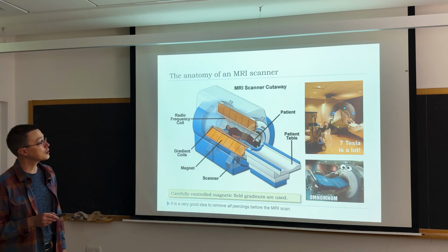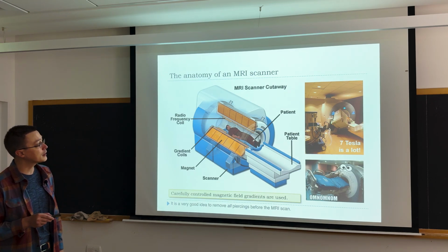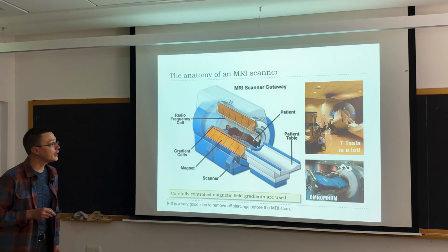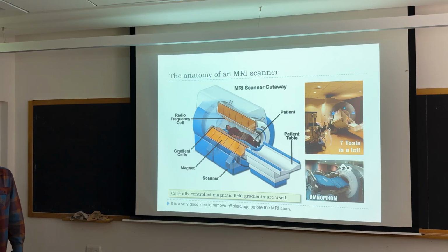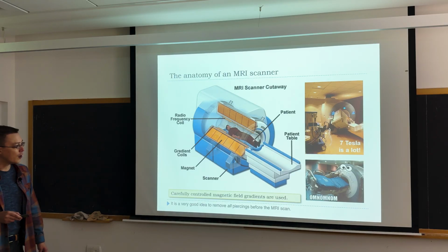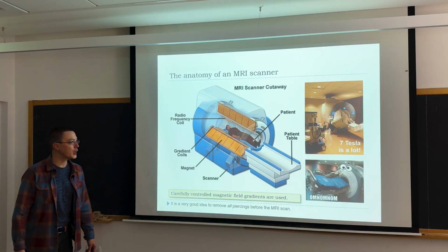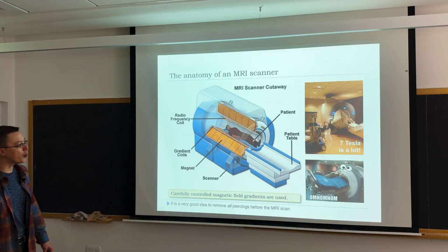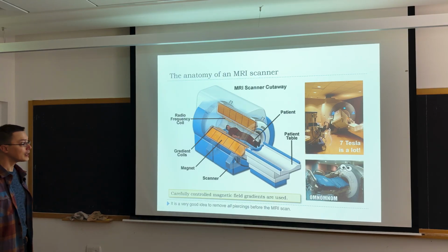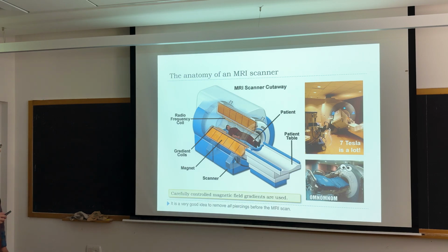This is a nurse trying to roll a ferromagnetic trolley past a magnet with a predictable result. So what you do need then is to de-energize the entire thing, pull the trolley out or pull this ferromagnetic bed out. You know, there are airport style security gates at the entrance to MRI facilities, because if God forbid you have a piercing somewhere in your body, it will be torn out. So yeah, one has to check very carefully for ferromagnetic substances in this case.